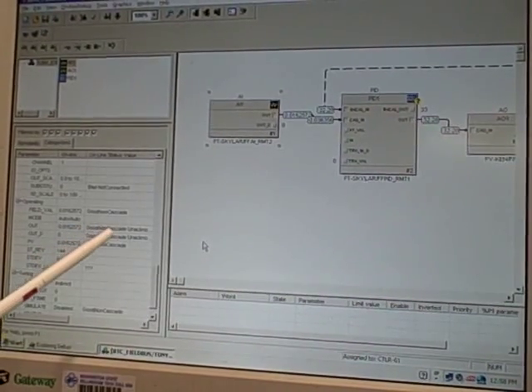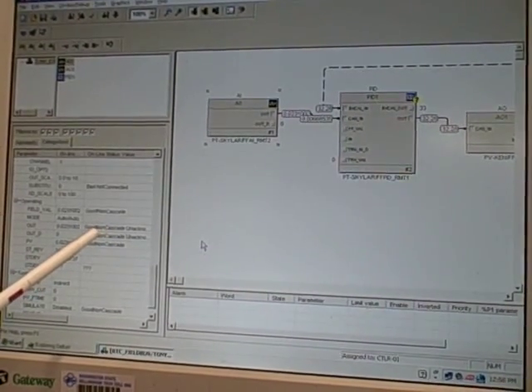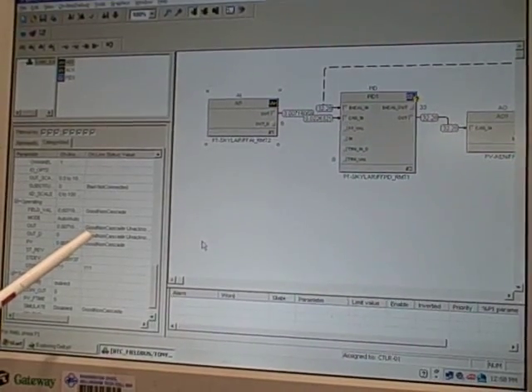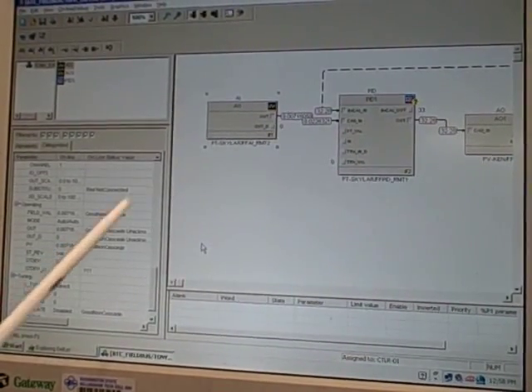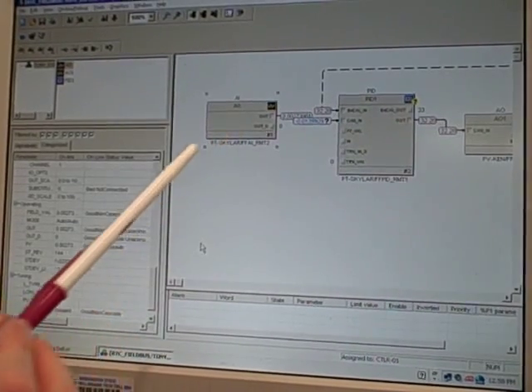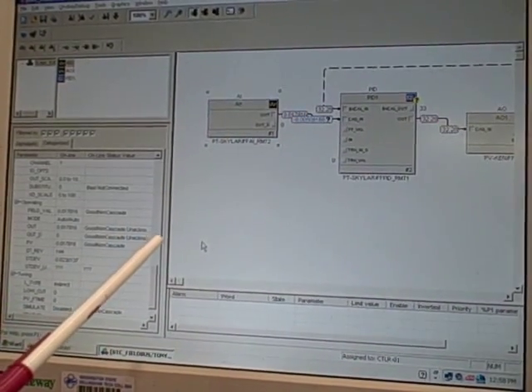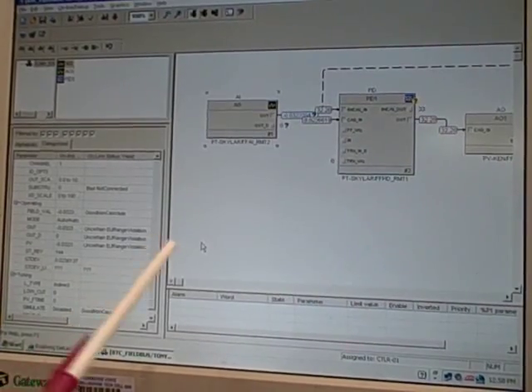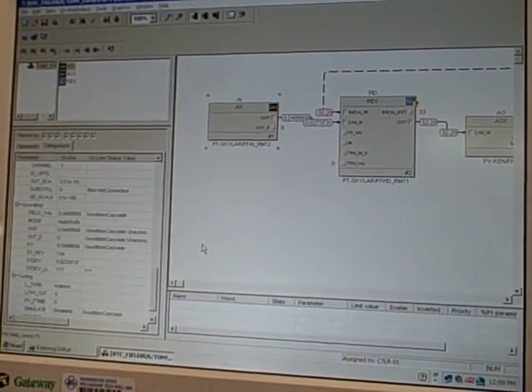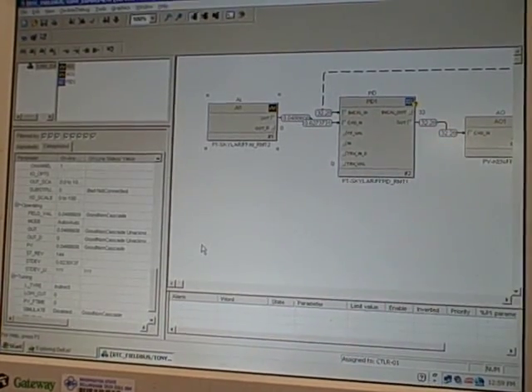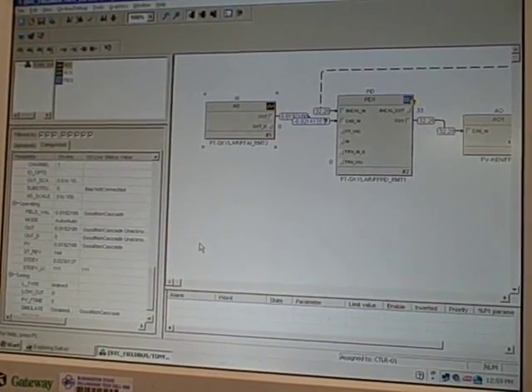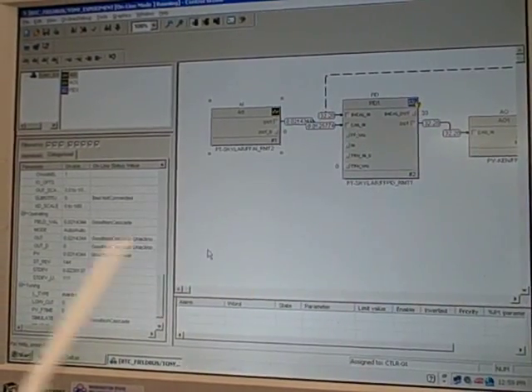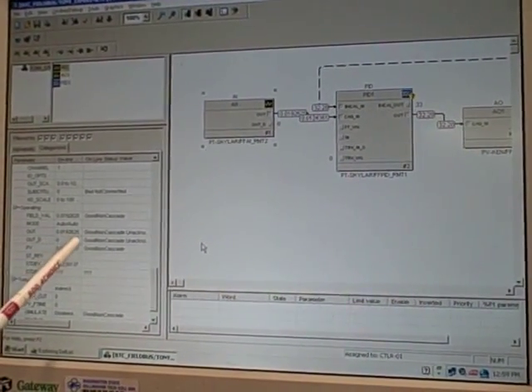And then in a moment it will probably switch to uncertain. The reason it's doing that is because we've configured the range of that transmitter signal to be 0 to 250 inches of water. Right now it's not measuring anything at all, and just the noise that occasionally pops up is driving that signal occasionally in the negative direction. When it goes negative, that is below its ranged value, 0 to 250, and so it flags an alert.